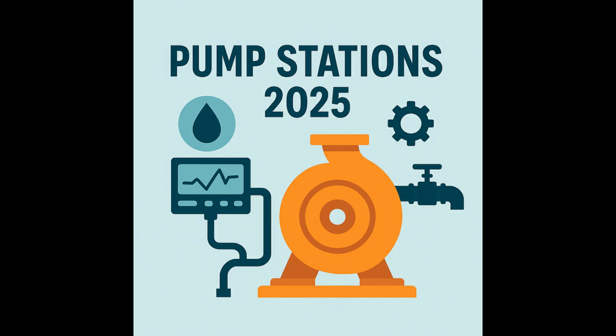Yeah. If pump stations are essentially the heart of our water and wastewater systems, what's the fundamental problem that's been plaguing these hearts for so long? What are we really trying to solve here? That's a great question, and it's surprisingly simple at its core. Pumps are often designed for those absolute peak demands, the highest flow rates you could possibly imagine. Right, the worst case scenario. Exactly. But here's the reality. Most of the time, they operate at average or even low flows. So this mismatch, it means they're constantly forced to run outside their optimal efficiency range.